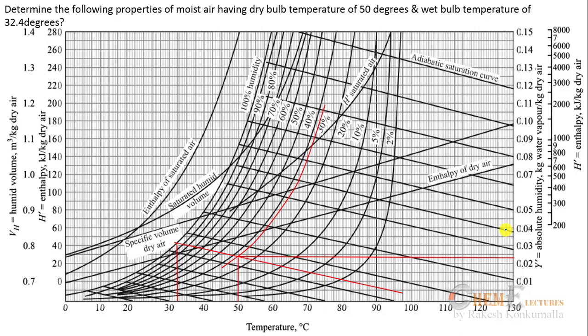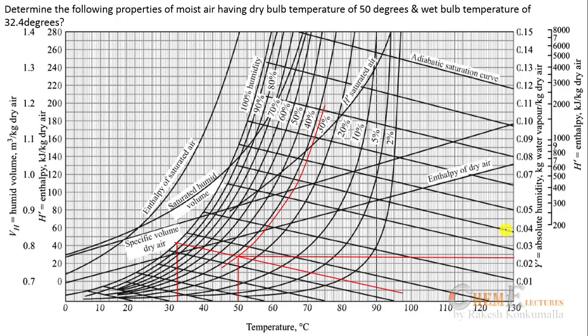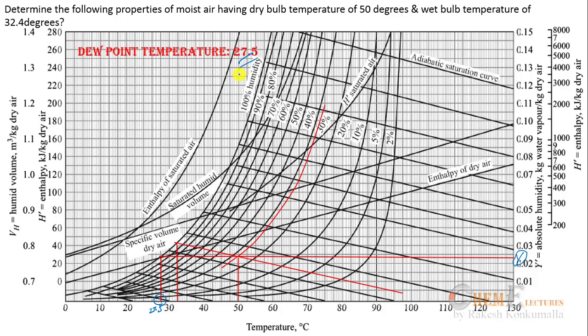Now finding dew point from the chart. I have the absolute humidity value; extending this line horizontally to the 100% humidity curve and then taking a vertical line down to the temperature x-axis gives the dew point temperature. This reads as approximately 27.5°C.